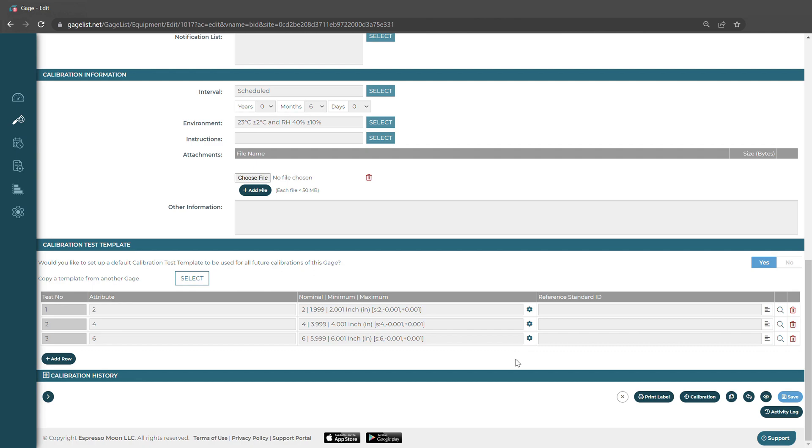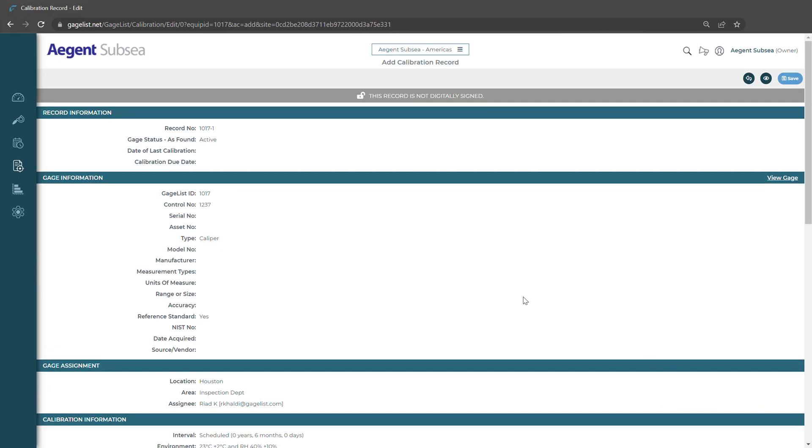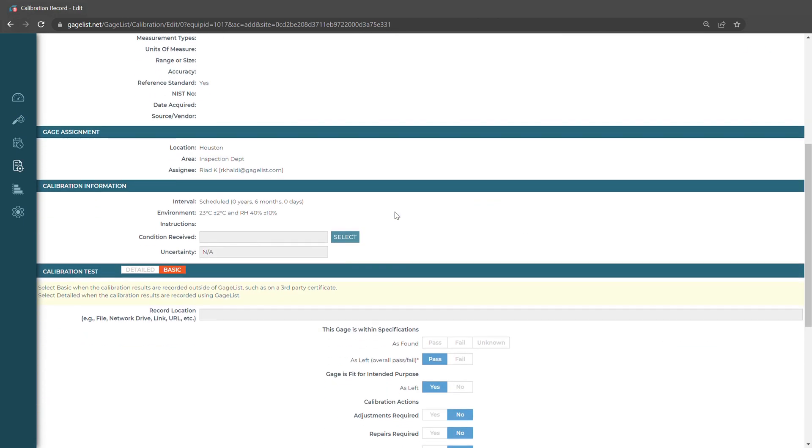Now that we have that set up, we can go ahead and add our calibration record. We'll click the calibration button. If we scroll down to the calibration test section, we can choose what kind of test we want to perform.